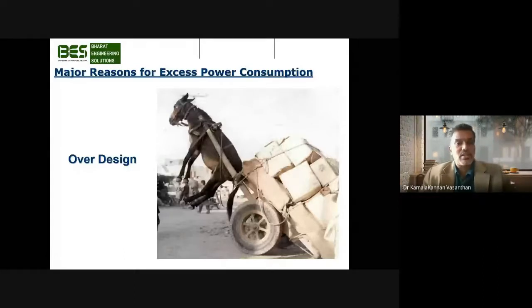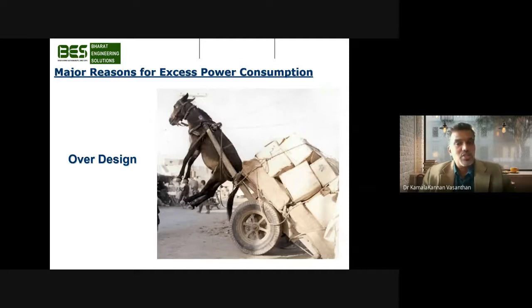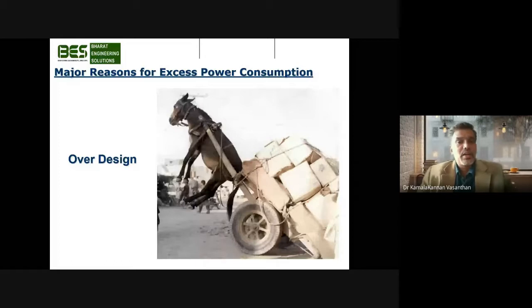And when it reaches the subcontractor, he adds another 10 to 15%, an average of 10% we see overall. And when it reaches the dealer or the manufacturer, again another 10 to 15%. So overall, while we visit sites and do energy audits over the pumps and systems, we see almost around 30 to 40% of the pumps being oversized, an average of 30%, and it depends upon the kilowatt ranges too.